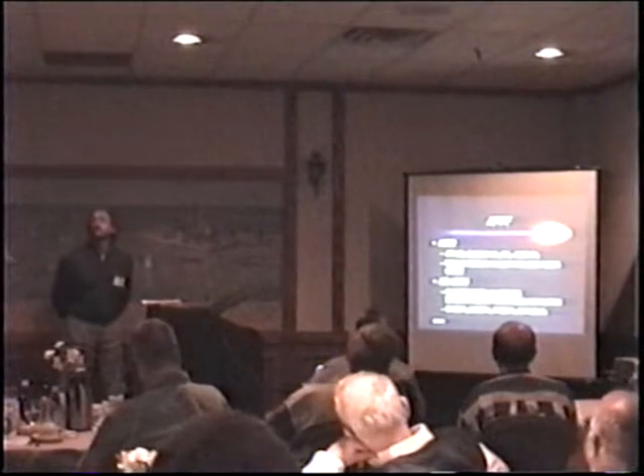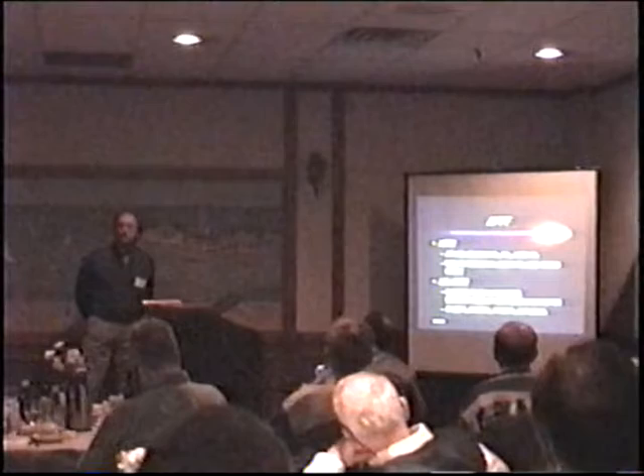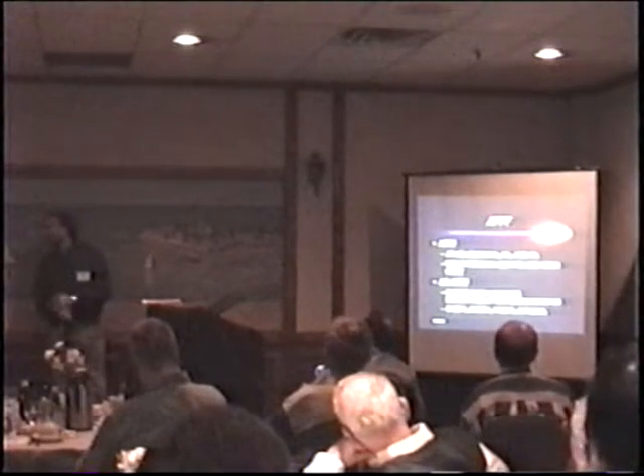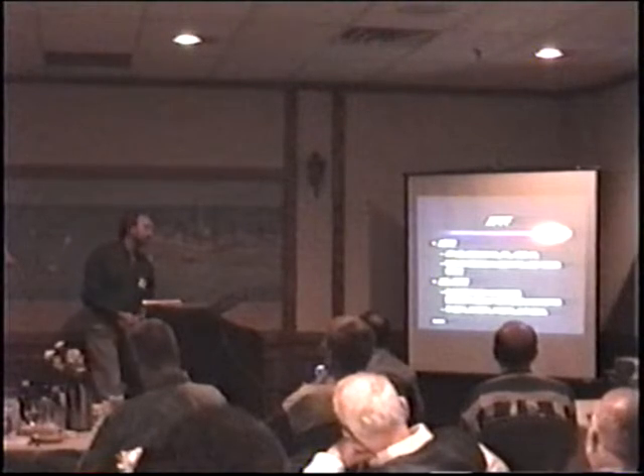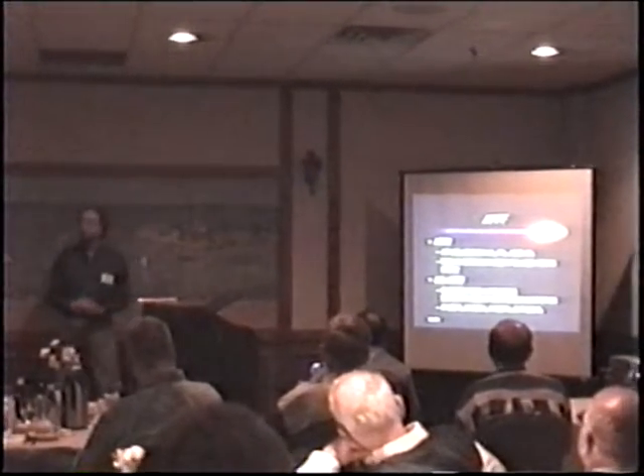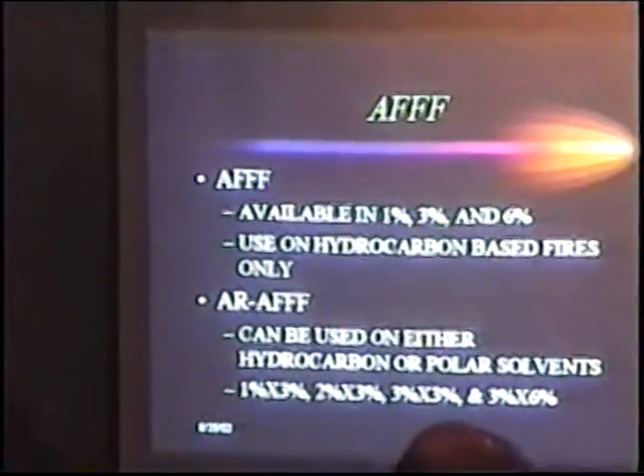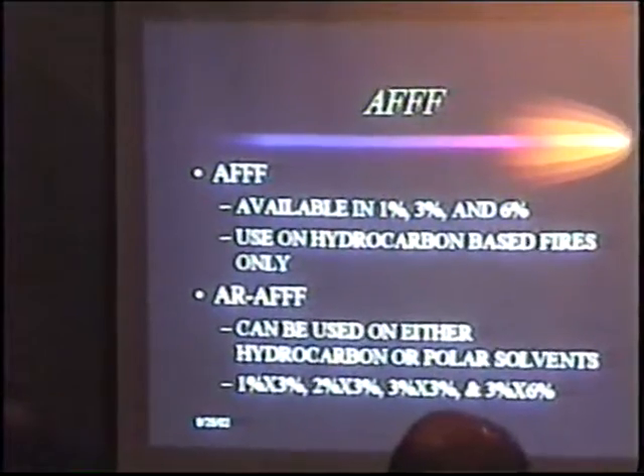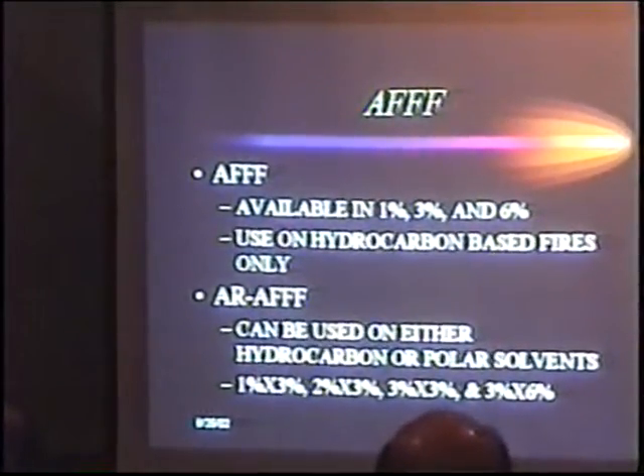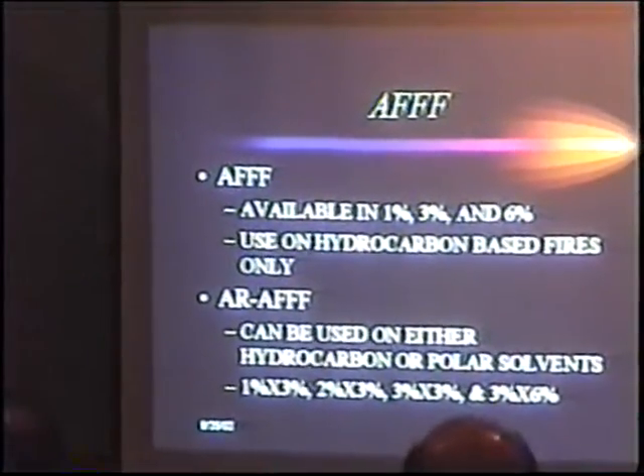You can use this on either hydrocarbon or water-soluble flammable liquids. Now, over the years, back when it first came out, it was a 6 and a 9. 9% on polar solvents, 6% on hydrocarbons. Then they improved it down to 3x6. Got down to, I suppose, in the early 90s, it came out with 3x3. Started cutting into our tank sizes, obviously. And now, of course, you can use 3% on hydrocarbons, 3% on the polar solvents.